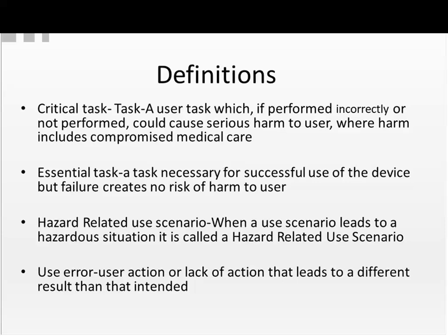So essential task is necessary for the use of the device, but a critical task is where harm can happen to the user. A hazard-related use scenario. If a use scenario leads to a hazardous situation, it's a hazard-related use scenario. Use error. User action or lack of action that leads to a different result than that intended.